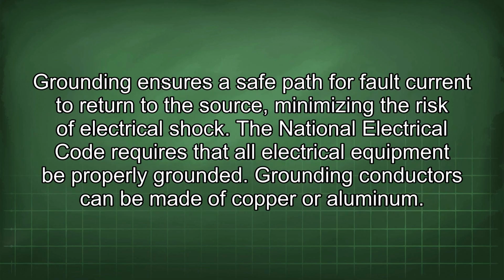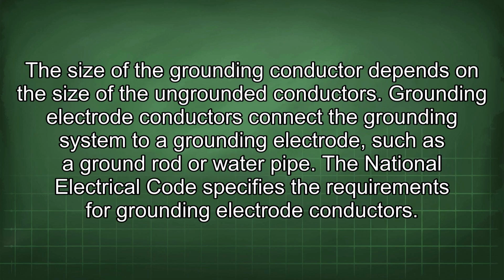Grounding ensures a safe path for fault current to return to the source, minimizing the risk of electrical shock. The National Electrical Code requires that all electrical equipment be properly grounded. Grounding conductors can be made of copper or aluminum. The size of the grounding conductor depends on the size of the ungrounded conductors. Grounding electrode conductors connect the grounding system to a grounding electrode, such as a ground rod or water pipe. The National Electrical Code specifies the requirements for grounding electrode conductors.